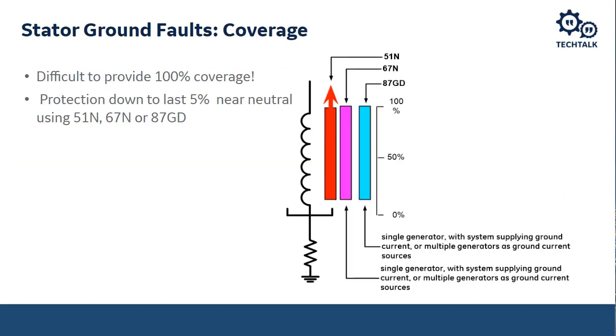So as with the high impedance ground fault protection, we can look at the various methods to protect a low impedance grounded machine. And we notice that all of these methods pretty much give you good coverage. It's very difficult, probably impossible, to get 100% coverage, however, because if we have a fault very close to the neutral of the transformer, it's the same thing as bypassing that grounding resistor. So you're basically bringing that ground up to the ground of the transformer, and you're not going to be able to detect that because it's not going to be any ground fault, right? So it's going to be very low or close to zero ground fault current. So for that last couple of percent of the generator, you will not be able to reliably detect to give you 100% coverage. And that might be okay because you're still continuing with your process.